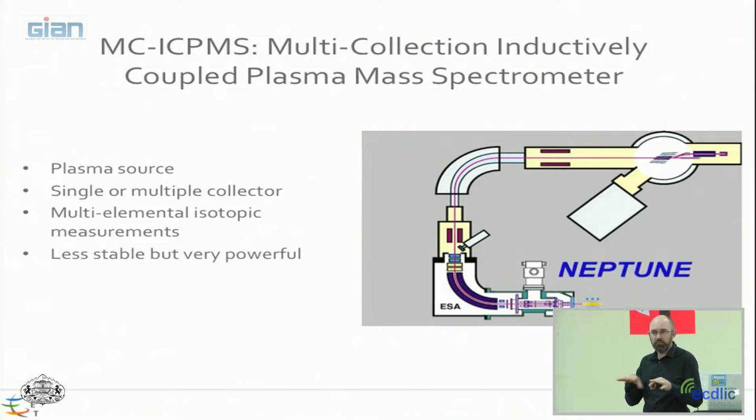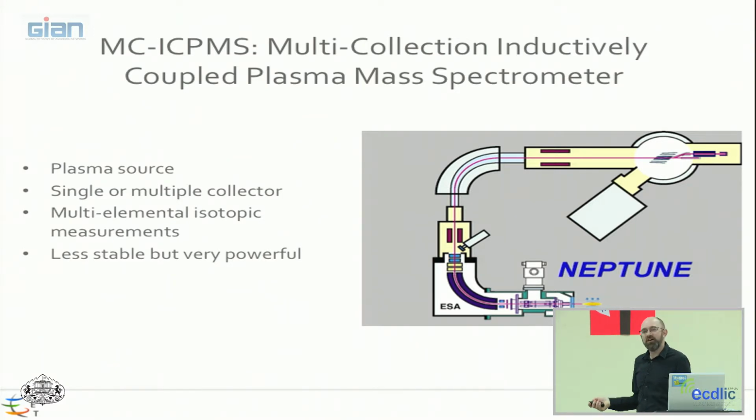You tune your collector, because all will be ionized at the same level, more or less. Okay? Of course, it's not the case. People thought about that at the beginning of the ICP-MS, but it's not the case. You still need to purify. Because I'm a TIMS guy, I find these machines less stable. I prefer my machine, okay? Because the plasma is just, I finish.